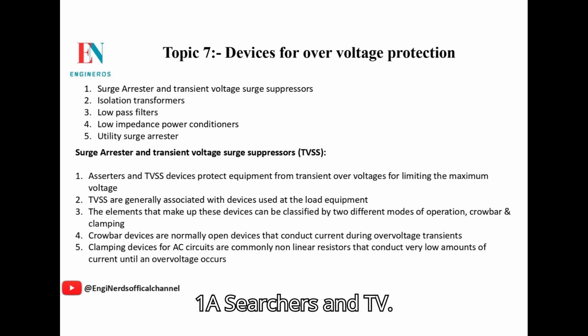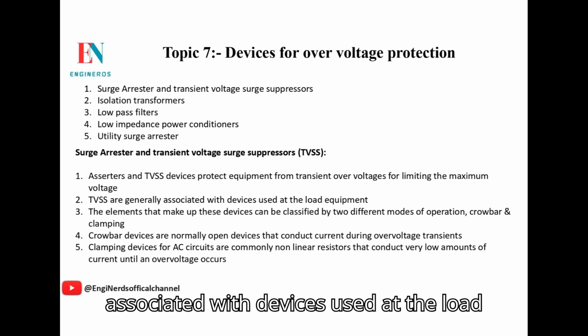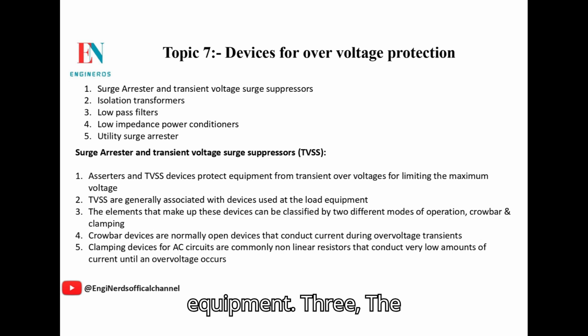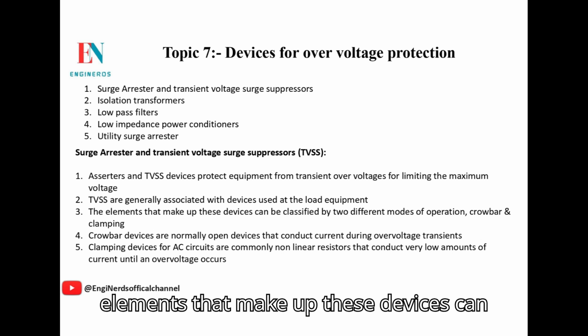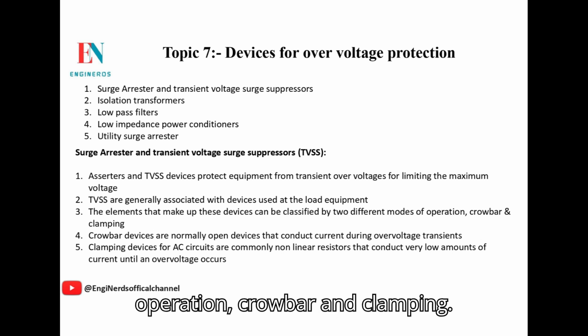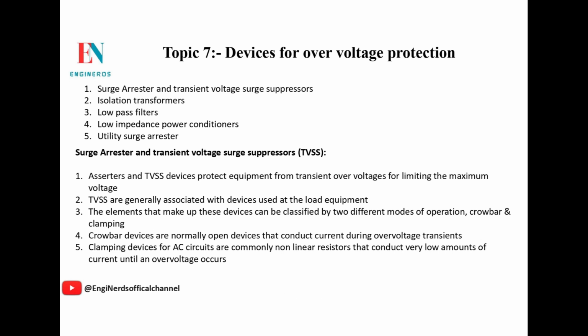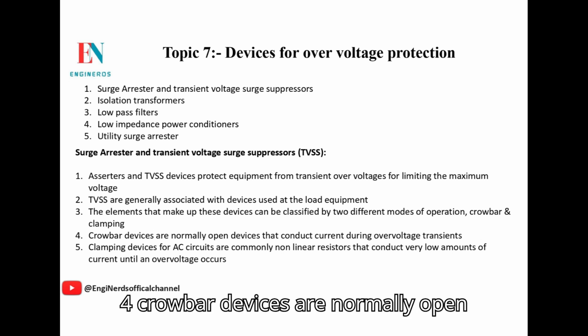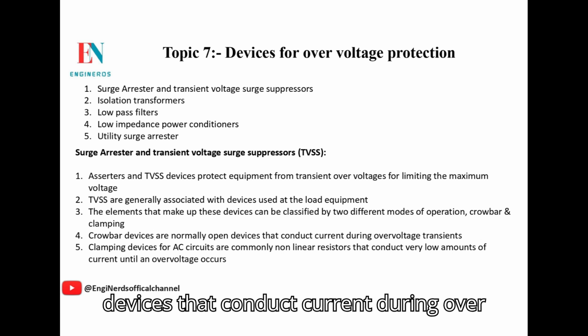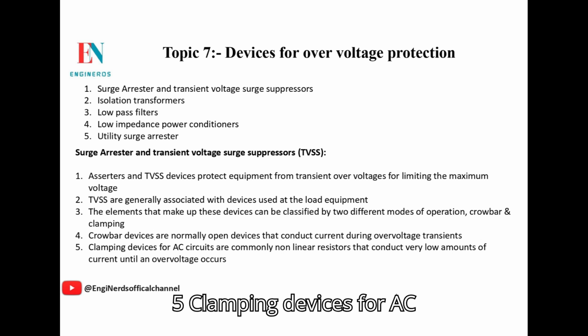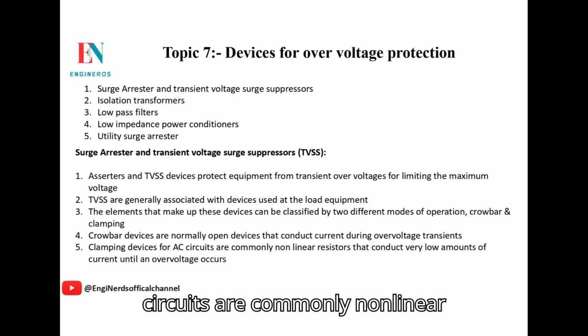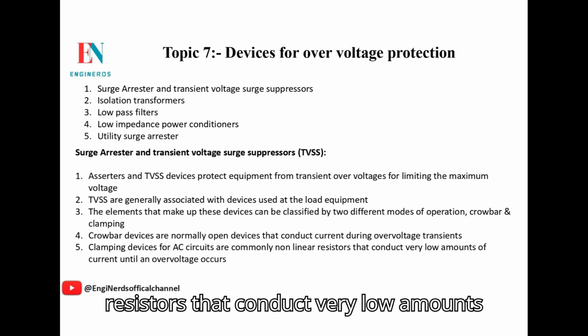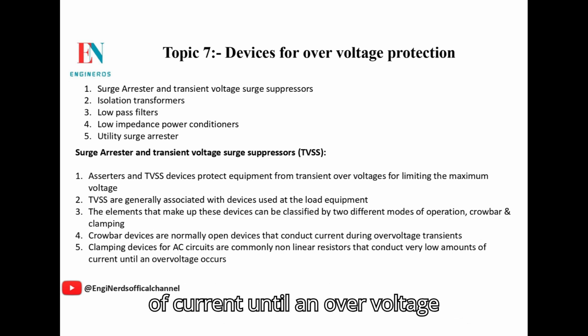1. Arresters and TVSS devices protect equipment from transient overvoltages by limiting the maximum voltage. 2. TVSS are generally associated with devices used at the load equipment. 3. The elements that make up these devices can be classified by two different modes of operation, crowbar and clamping. 4. Crowbar devices are normally open devices that conduct current during overvoltage transients. 5. Clamping devices for AC circuits are commonly non-linear resistors that conduct very low amounts of current until an overvoltage occurs.